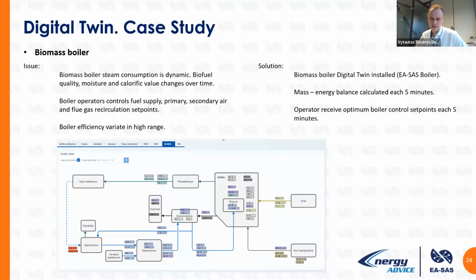What is the principle? Vadim is asking, what is the principal difference between the SCADA automation system and digital twin? In fact, it's absolutely different, because you have a SCADA system and you use the SCADA system. If you buy digital twin technology, the SCADA system still stays as it was previously in your company. But the digital twin collects real-time data from your SCADA system, from your controllers, from the SCADA, I mean from the SQL database or from the controllers directly, in parallel to the SCADA system. But the digital twin calculates automatically, like a monitor, what's happening inside, and gives you optimum set points. I mean optimum, what is really needed for you, and these set points you usually put back to the SCADA system. So digital twin is like a system which is hierarchically on top of the SCADA system.